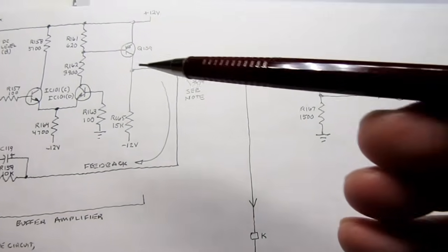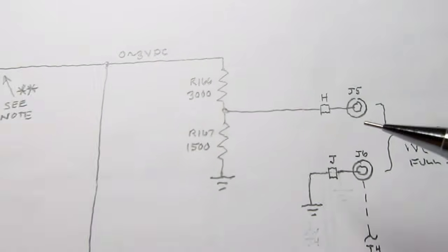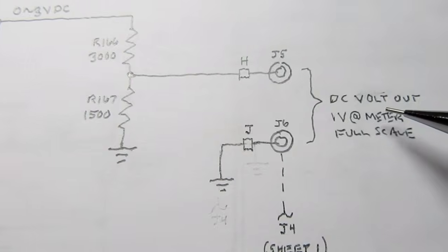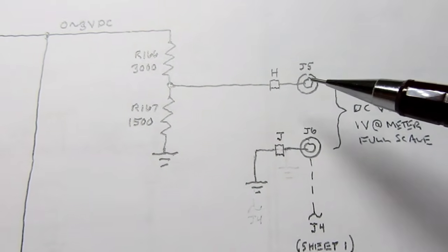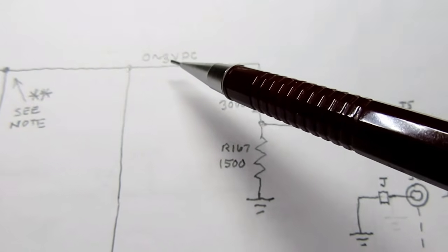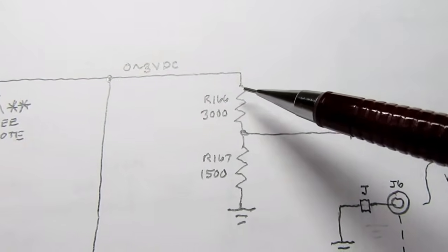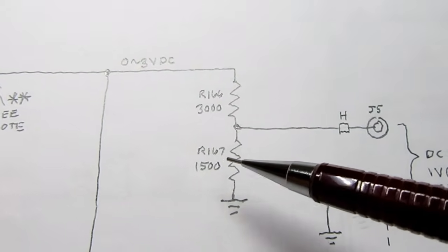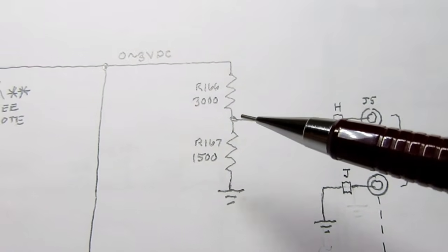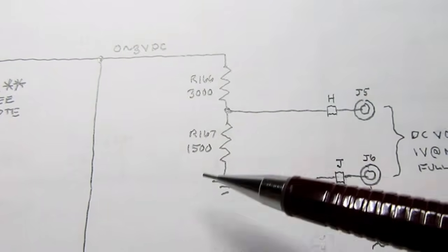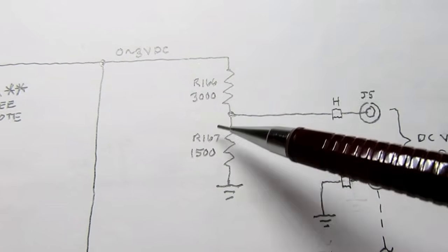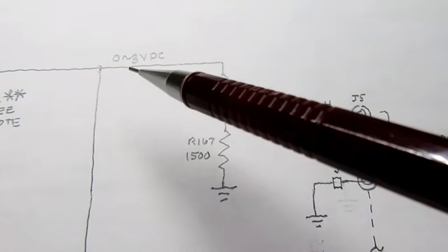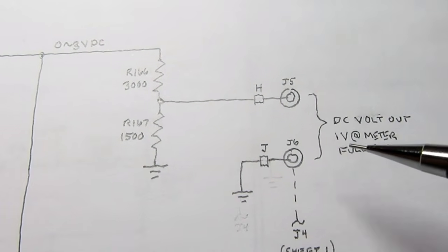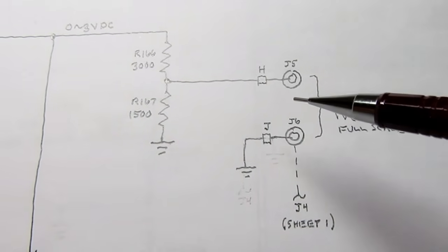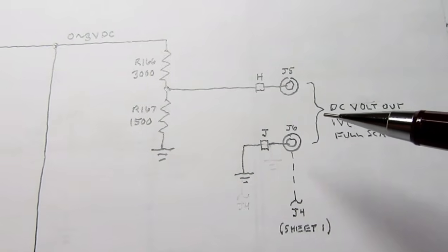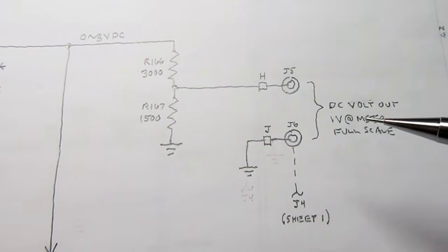And this goes 3 places, which is one reason why I needed this buffering here. The first place it goes is a pair of output jacks on the rear panel, the DC volt output. One of the jacks is tied to ground, the other one is tied to this 0 to 3 volt DC signal by way of this 2 to 1 voltage divider. Well, it's actually 2 over 1, so 2 parts are going to be dropped here and 1 part's going to be dropped here. So you have 3 volts up here, there's going to be 2 volts dropped here and 1 volt dropped here. So we've turned a 0 to 3 volt signal into a 0 to 1 volt signal. The 1 volt corresponds to meter full scale. So this is what you can connect up to an external meter or chart recorder or something else that might need to monitor the signal that's coming into the meter.